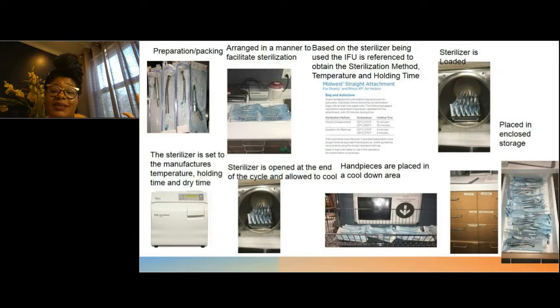So this is basically almost all, and not really going too into depth of what it takes to reprocess a handpiece. Preparing it, arranging it in a manner to facilitate sterilization based on what sterilizer is being used. Check the times, okay? That's important. Loading the sterilizer properly is also important. Setting the time and temperature. And I will say it again, once the sterilizer cycle is done, the handpieces or devices are allowed to cool down inside of that sterilizer prior to them then going to the cooling down area to be placed within their storage locations.